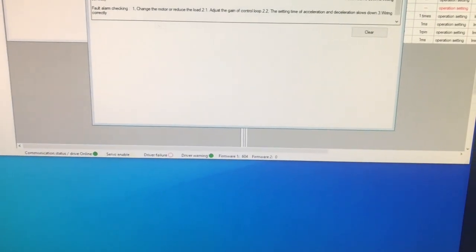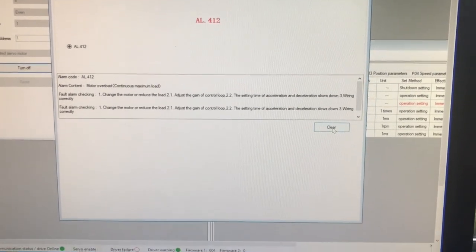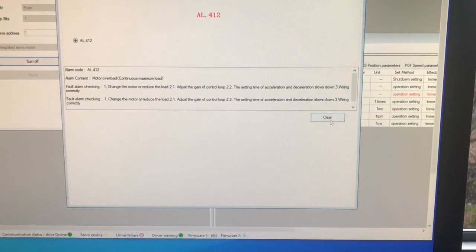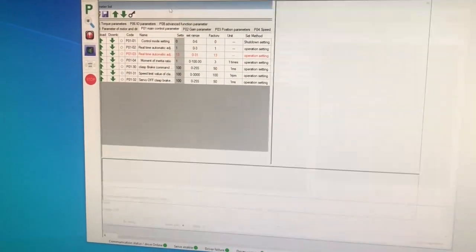So now I have these warnings. The fault was motor overload. Let's see if I can clear it. I found I can only clear the position fault — any of the overload faults I can't clear. I actually have to disconnect my system. And then it's back to normal.